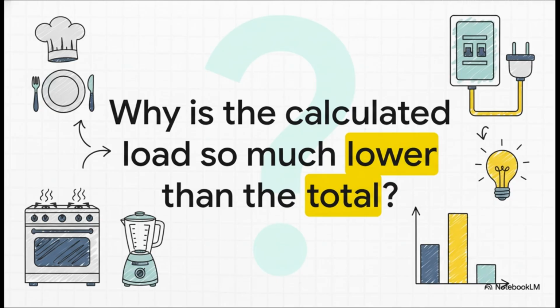Let me guess, it's higher. Much higher. It's 50% of the amount over 200 kVA plus a base load of 200 kVA. Okay, wait, so the multiplier is way higher, 50% versus 10%, and the starting base load is higher too, 200 kVA versus 160 kVA. Exactly. That's a significant difference just based on whether the cooking is electric or gas.